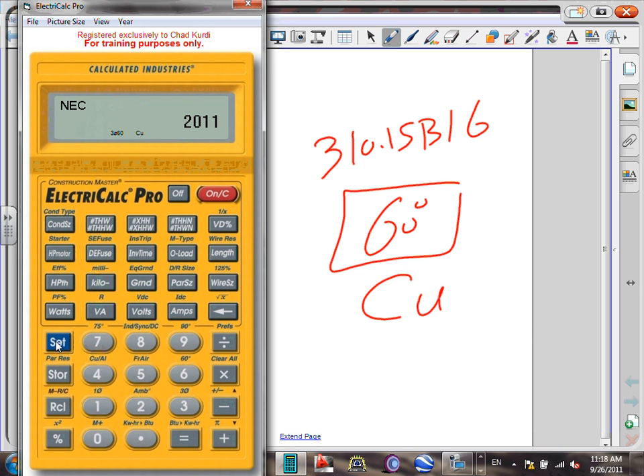First of all, I want you guys to change it to 3-phase. Go set, and do you see where 3-phase is? The number 3. Set number 3. That will change your calculator to default to 3-phase. Now you're doing a 3-phase system. Did you guys see that? Set 3. That will get you to 3-phase. Okay, now let's change to aluminum. Set 4. Can you guys see set 4 right above it? Cu/Al. That will change me to 3-phase 60 hertz aluminum.